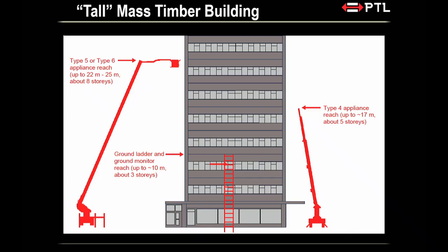Spraying water upwards. I mean, you're a structural engineer, you can tell me, it's all about gravity, it is hard work, right? So which is why 18 meters and 10 meters come in, so that firefighters can deal with it nicely. Because any taller, they can't use these appliances. They have to go into your building.